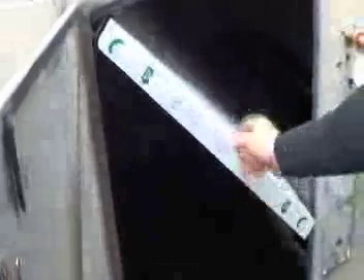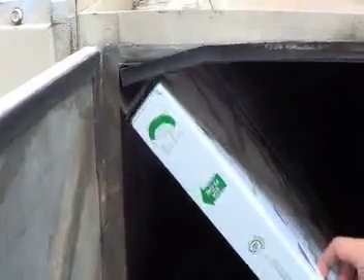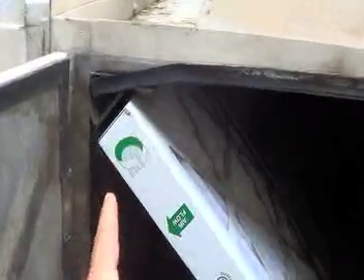Well, the problem with these filters is they're individually boxed filters. Their design alone prevents anybody who uses them from achieving a complete seal. Air mimics water. It follows the path of least resistance and will expose any gaps or bypass. And as you can see, there is tremendous bypass both around and between the filters where they meet. And this has a negative effect on these coils.